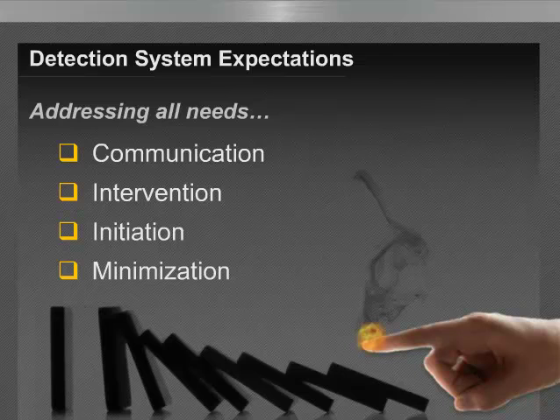Also look at intervention, and that is the opportunity to investigate pre-alarm conditions, and initiation of sequential systems or procedures such as fan shutdown, suppression release, transfer of data, and so forth. And also minimization, and that is, early response will likely reduce the impact on operations. So for instance, you may not have to shut down operations, senior management may not have to get involved, and the fire department may not have to come out. And that's the intent of automatic detection systems. Ineffective automatic detection systems can break the sequence and not meet stakeholders' response expectations.